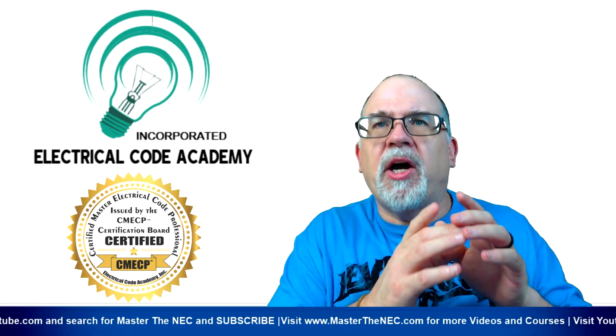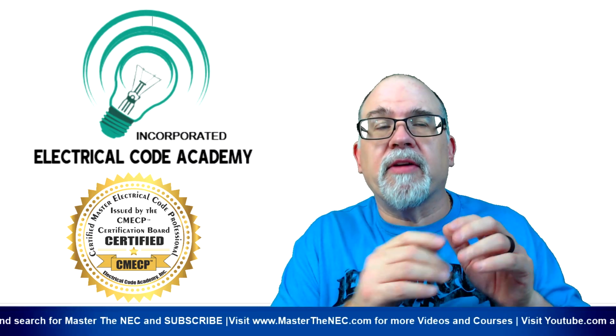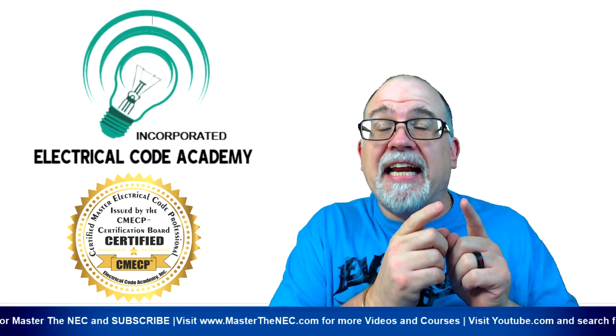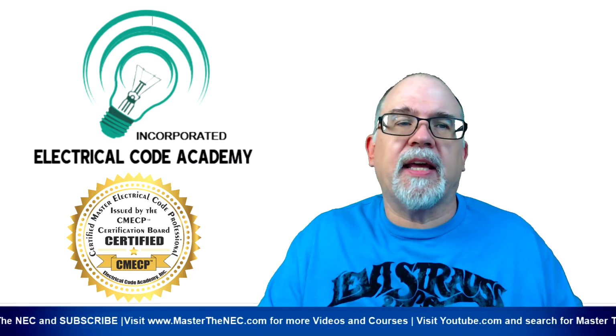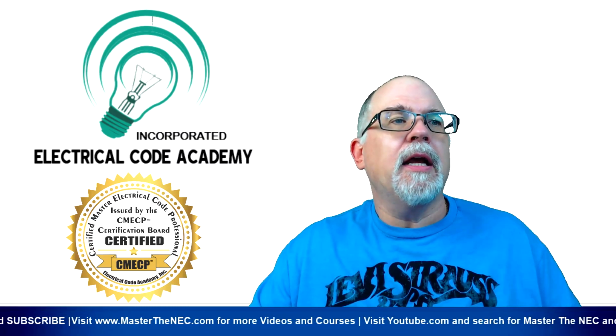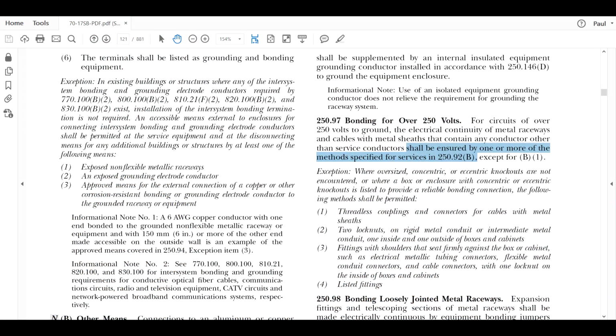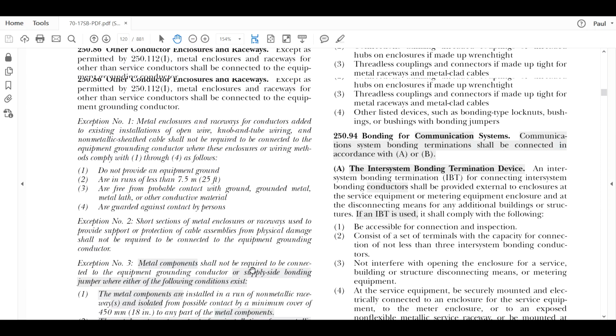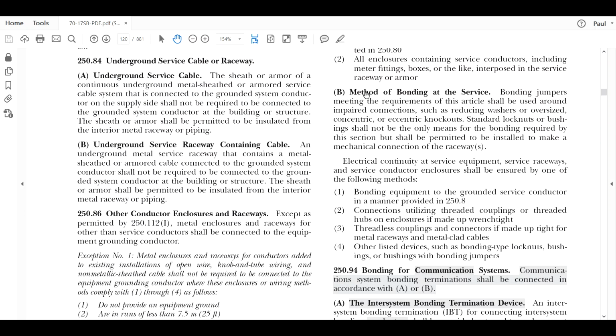And we have perfectly punched out openings. Let's go over to 250.92(B) and see what our options are. Okay, we're not looking at the exception yet. Another thing to remember is that we can't use exception B1, where we're making a connection to the grounded conductor in order to make that bond. But we've got 2, 3, and 4 that we could use. So let's go back to it. It's right here: methods of bonding at the service. Of course, we're not dealing with the service, but we're utilizing it like we're doing at the service.